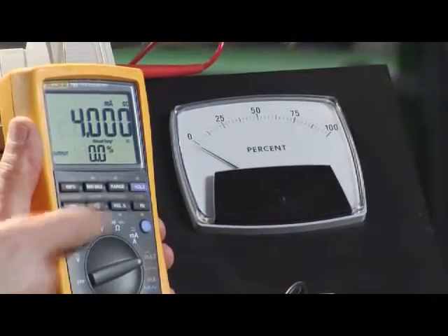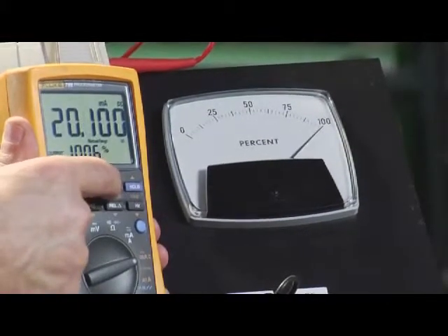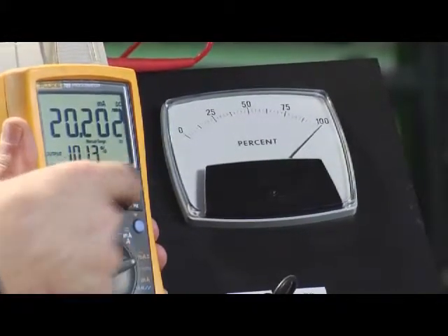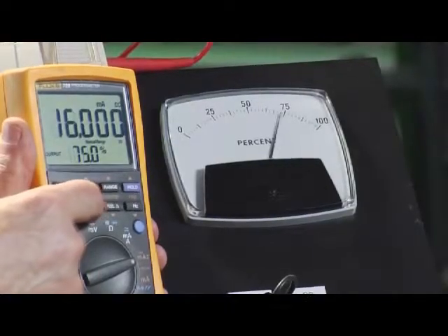You can go from zero to span and change the output in 25% steps, change the output in one tenth of a milliamp steps, or one microamp steps for fine tuning.